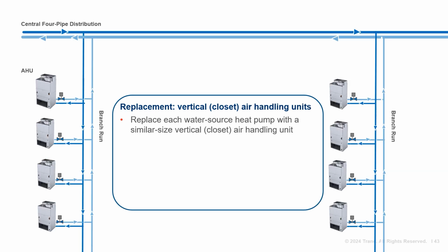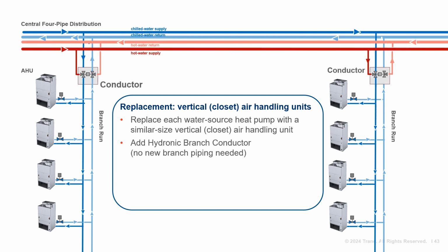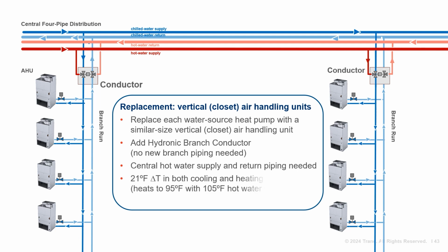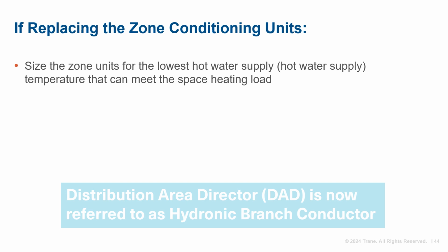In this case, each heat pump is replaced with a similar sized vertical air handler. A distribution area director is added that enables switchover for each area, reusing the distribution piping. Central hot water supply and return piping will need to be added to the building for this retrofit option to work. For this example, the dual-purpose coil in the vertical air handler is sized for 21 degree delta T in both cooling and heating. In heating, it can warm air from 55 to 95 degrees using 105 degree hot water. In conclusion, if the zone conditioning units are being replaced, size the zone units for the lowest hot water supply temperature that can meet the space load.